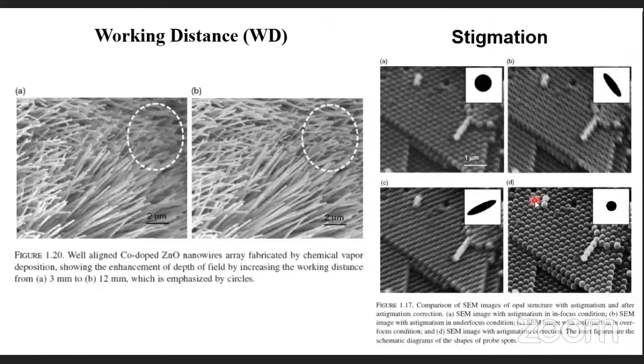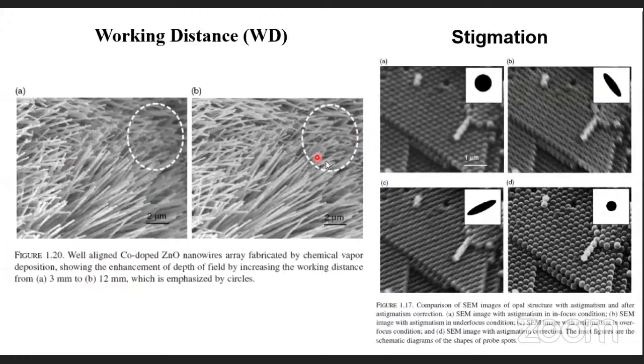Working distance is also very important. For our instrument, working distance can vary up to 40 mm — it is the distance between the lens and the sample. At a working distance of 3 mm, you can't see the perfect morphology, but at 12 mm working distance, you can see very clear needle-like morphology. These parameters are all adjusted by the technical staff.